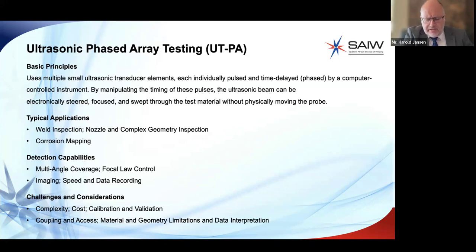Furthermore, the electronic focusing optimizes sensitivity at specific depths, enhancing resolution and signal to noise ratio. Imaging, in other words, the results can be displayed in real-time S scans, which is a sectorial scan, cross-sectional scans or B scans, and a plan view or C scans, aiding flaw characterization and reporting. The data recording of phased array ultrasonics facilitates full data storage for review, traceability, as well as auditing purposes.